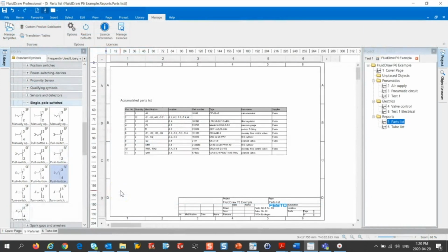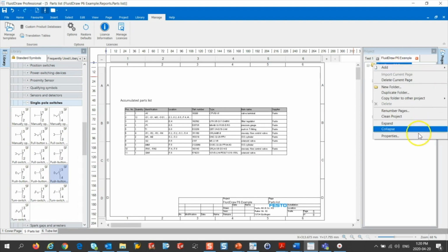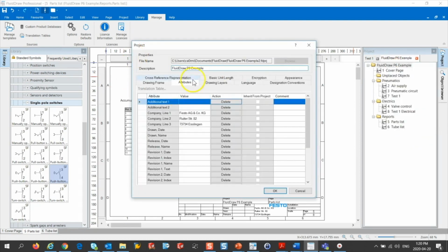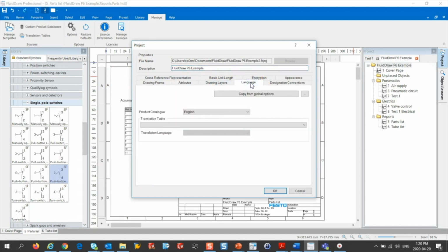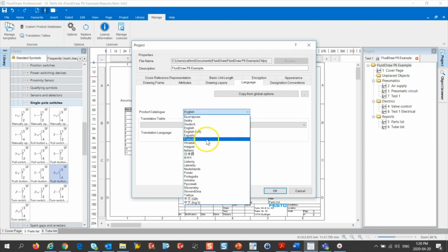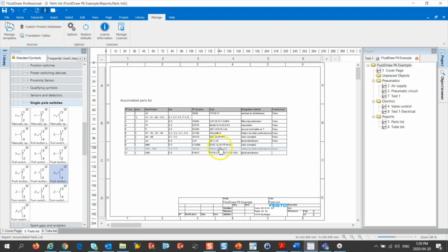One of the last things we're going to deal with is setting the languages for your project. There's a number of ways of doing this, and this would be very prevalent for our customers who deal with the large Spanish-speaking population in Mexico and southern United States, or in northern provinces, the ones dealing with Quebec. So first, Festo has a number of languages already preset. If you go under your global settings for your project, you can have a language tab. Here you can set whatever language you're looking for. Say French, click OK. And as you can see here, everything changes to French. But certain things don't, because they don't have properties, they're just text that's written in.